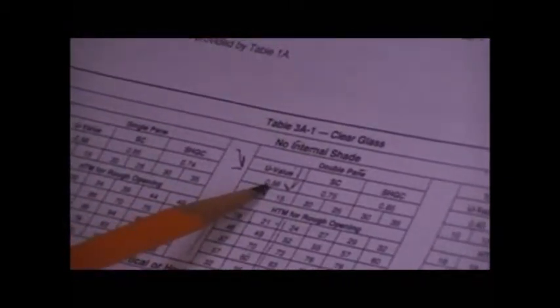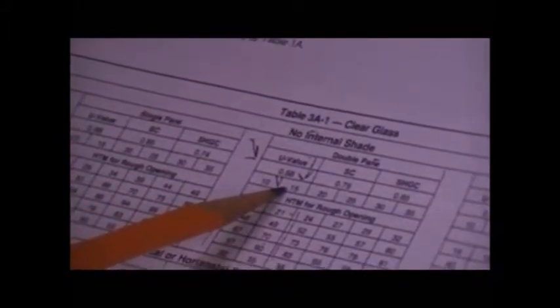We don't have any internal shading on our particular windows, and we're going to be looking under the 3A table. The U value shows a 0.56. That's not quite a big difference, but we're looking at our 15 degree differential more than anything else. That's the design cooling temperature differential. We also have to consider the orientation: north, northeast, northwest, east or west, southeast or southwest, or south.